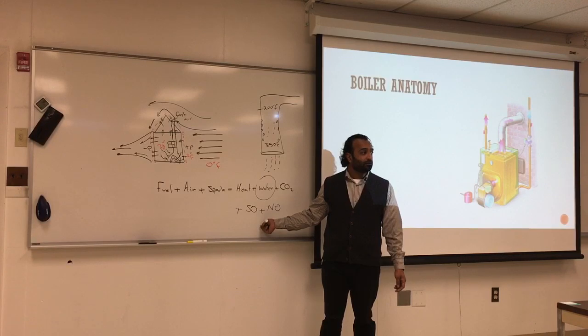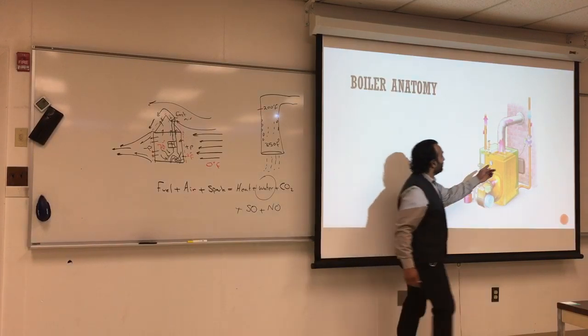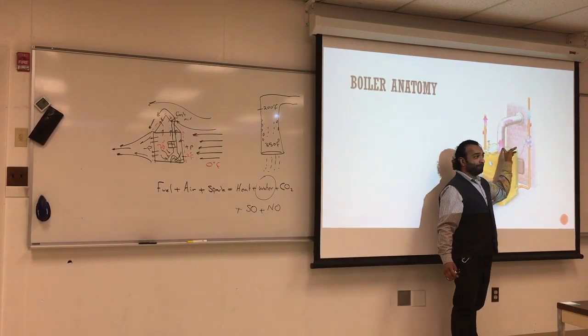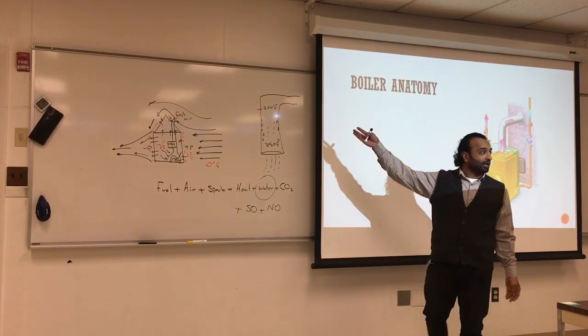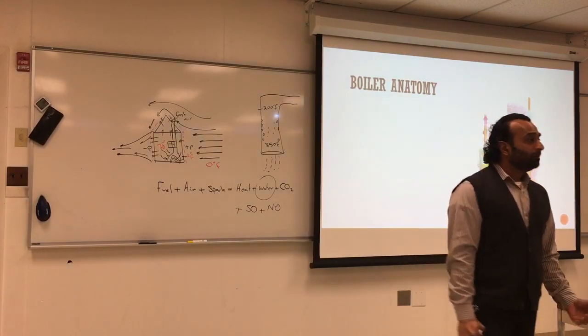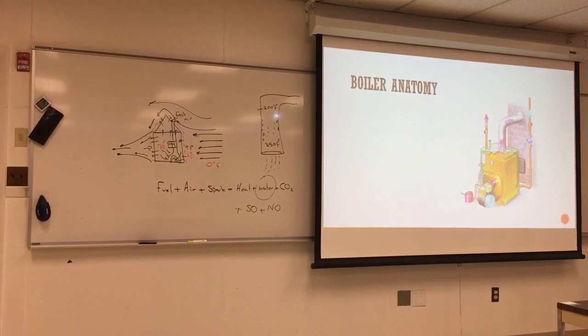What's the temperature when it leaves the boiler? We try to set it at 450 to guarantee that it will not condensate on the way out. By doing that, we kind of preserve the life of the boiler, but what else are we doing? We're wasting heat, right?